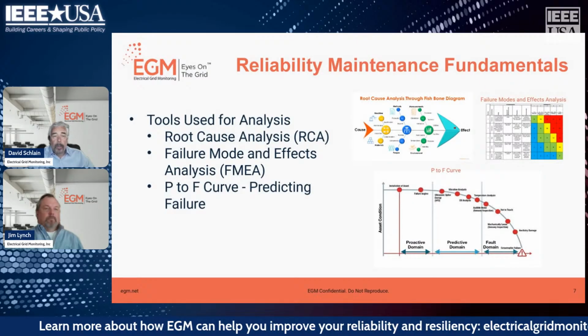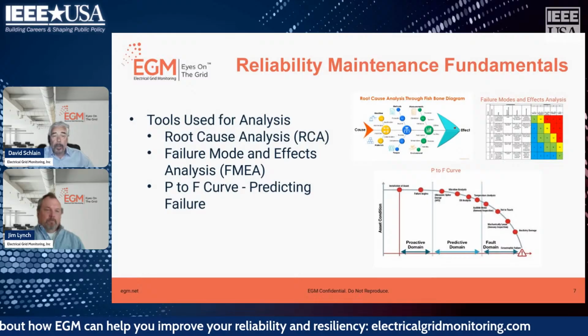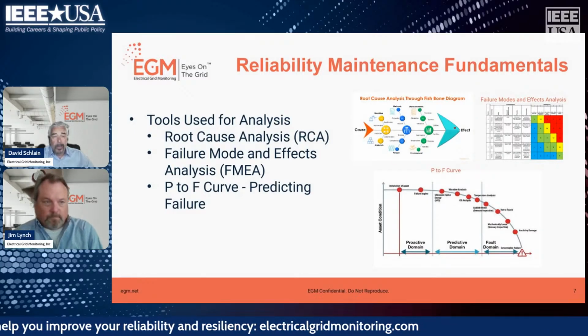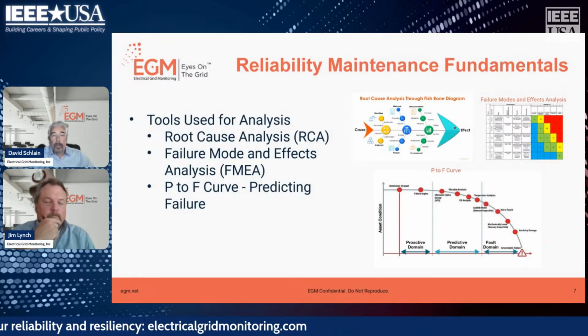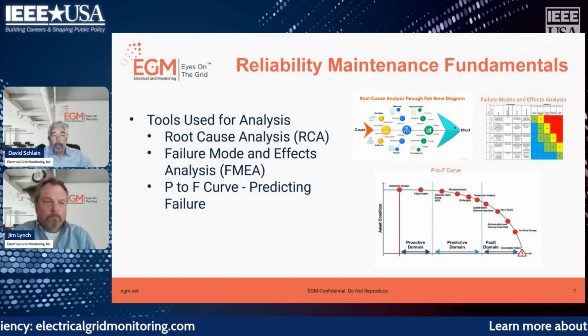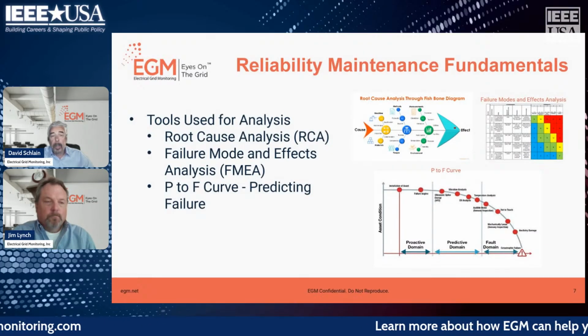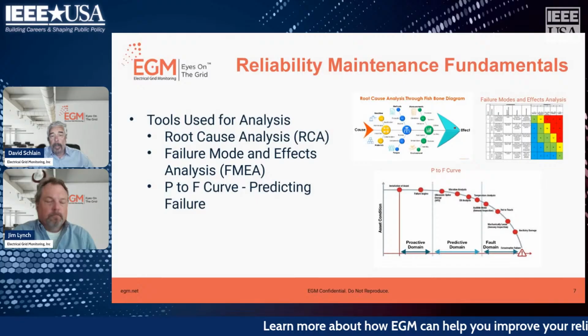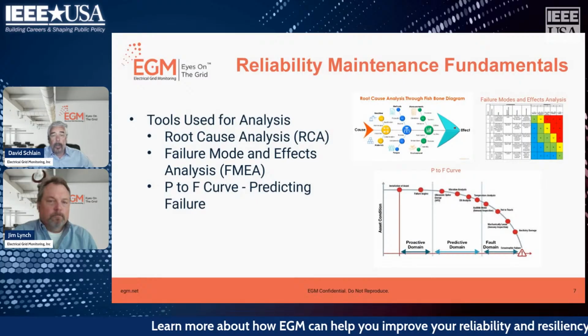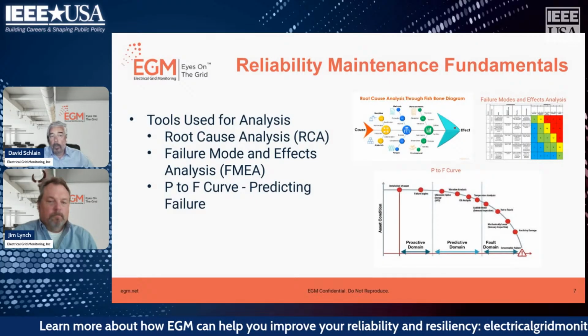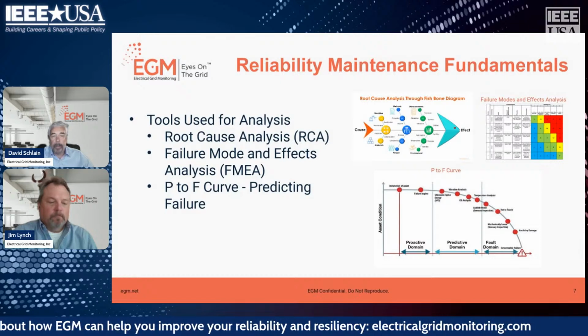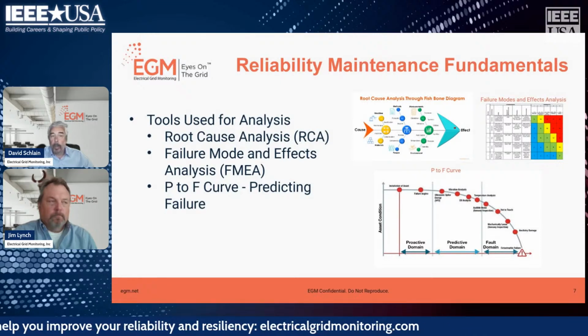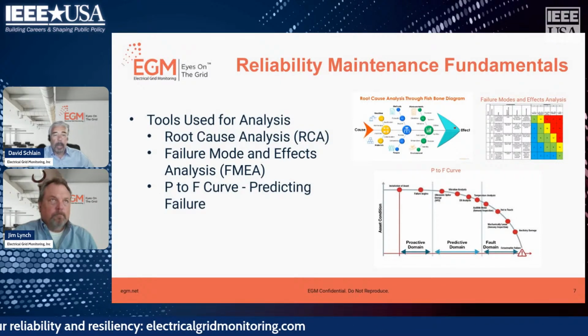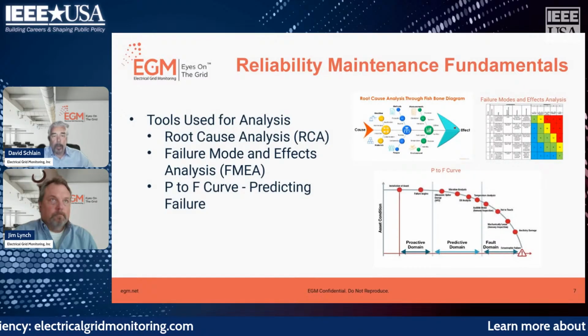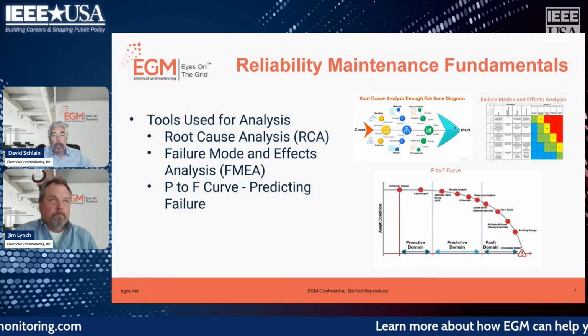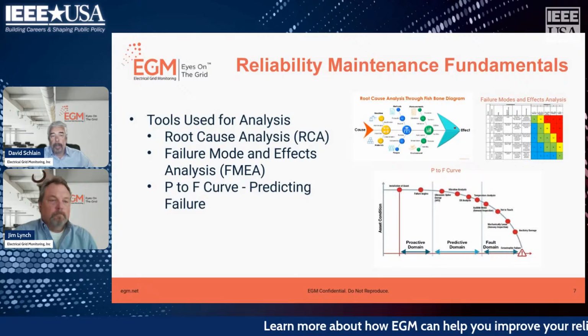Part of these unique failures, for instance, how do you determine the life of an overhead conductor? The manufacturer may tell you that conductor has a 15 to 40 year life, but with all the variability out there, you can't actually determine what that life is. It may be short-lived because of external factors like extreme heat, extreme cold, ice, high humidity, salt, or fog. All of these factors can significantly decrease the life of that conductor.